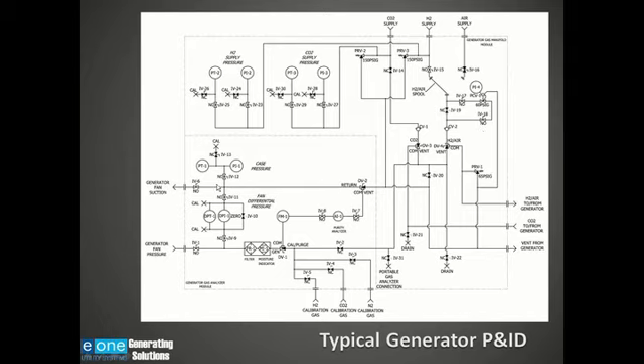Over here we've got the case pressure indicators and transmitters so that we know what the case pressure is. I'll show a slide later on that will show the importance of measuring the case pressure. Again, we have an indicator that will give us a local indication, and we have a transmitter that will feed a signal back into the control room. Again, we have the cal port with the isolation valve so that we can calibrate this unit without taking it offline.